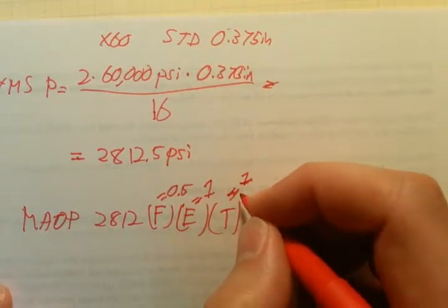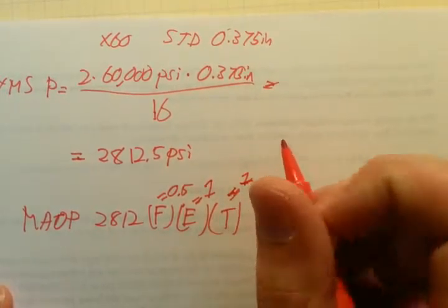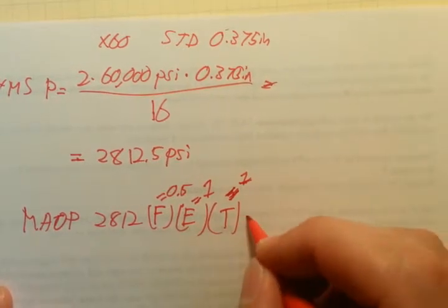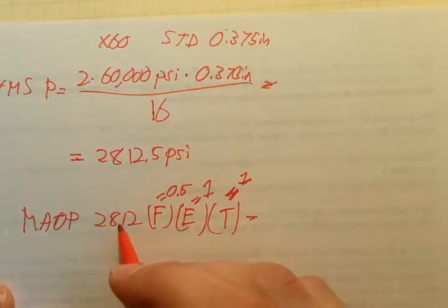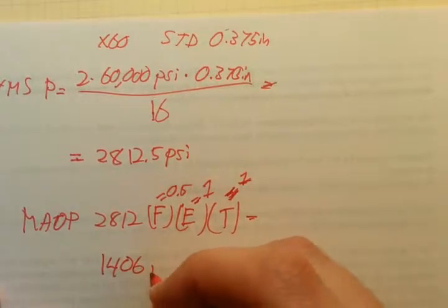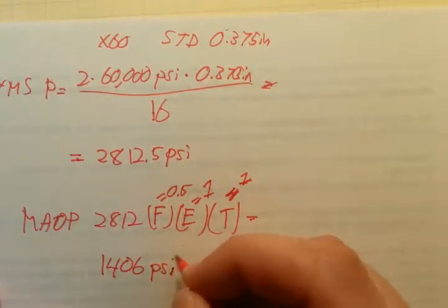Most of the time, unless you're dealing with process pipe, it's pretty safe to assume that's just going to be one. So we're basically just dividing by two this 2812, which gives us 1406 PSI rounded.